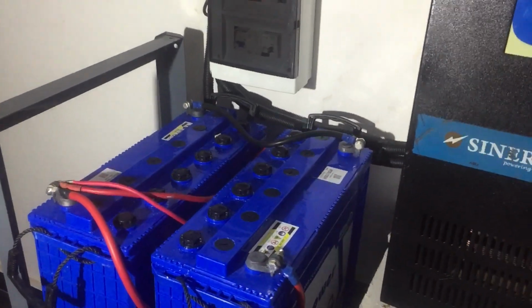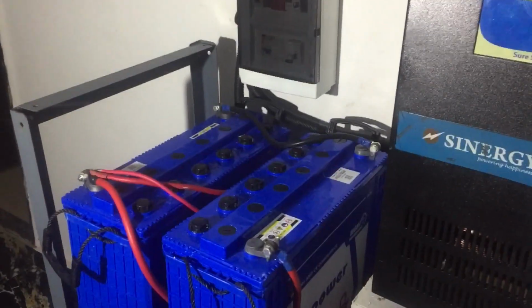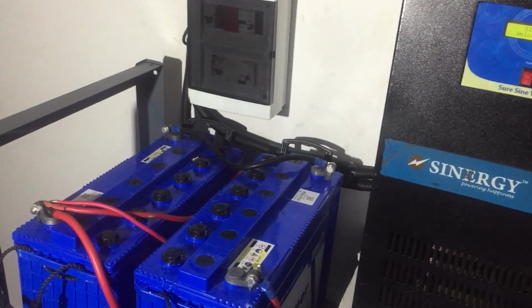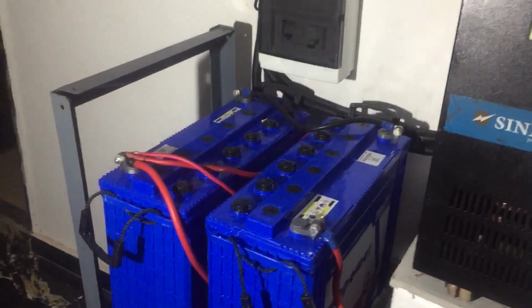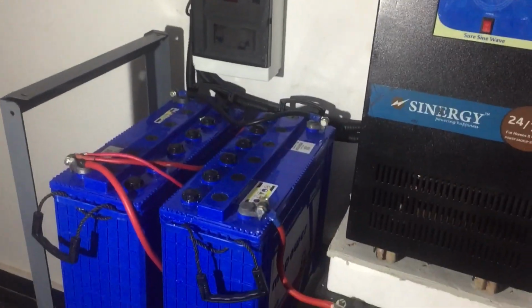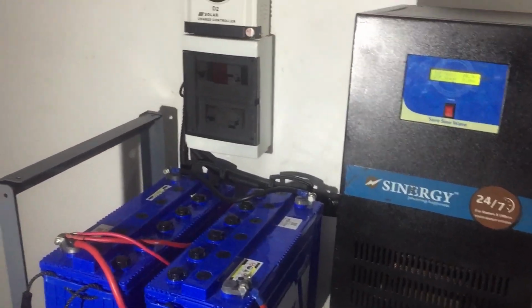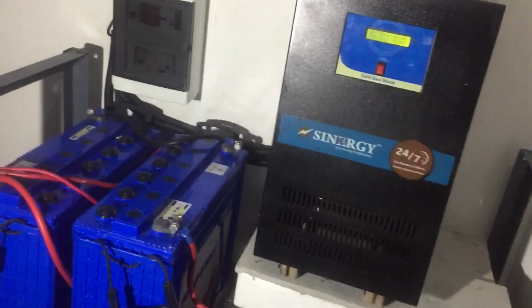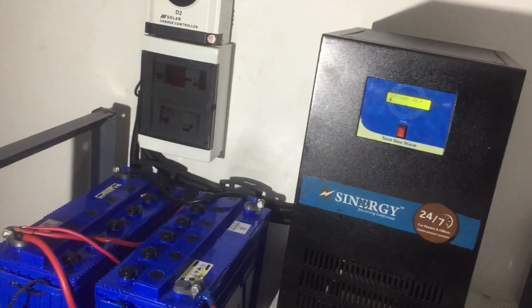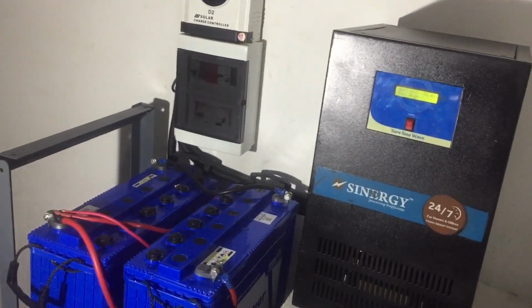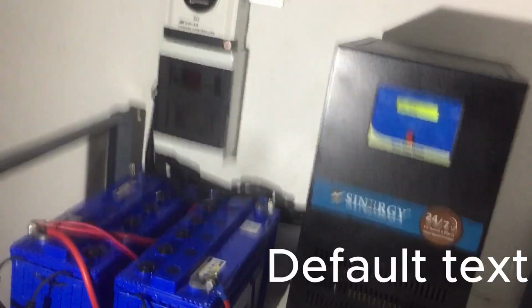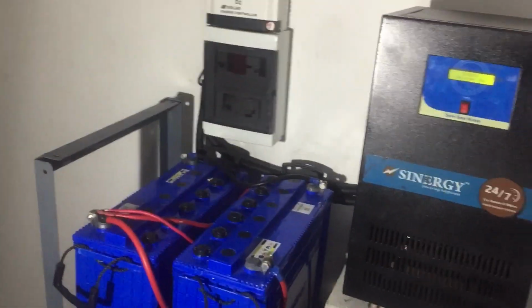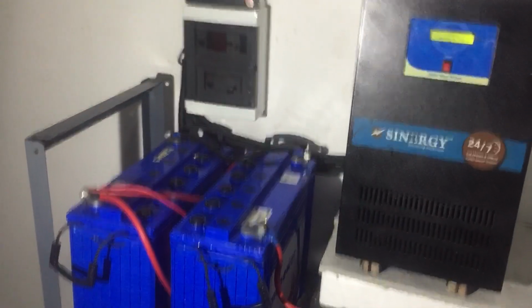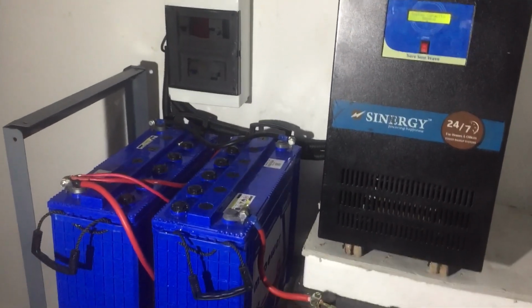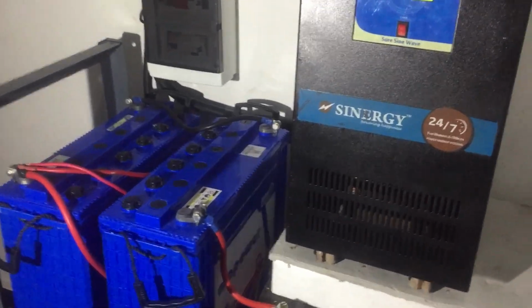Because like I said earlier, every inverter has its own programming. The type of battery is a command. You command the inverter on the type of battery you want it to charge. But if you command it to, for example, charge a tubular, or lithium, or any type of battery, and it detects a foreign body, which is a different type of battery, the charging system may not be very okay. So that's why you must ensure that it is the same type of battery. Very important. Now, this inverter you see here is a 5 kVA inverter.